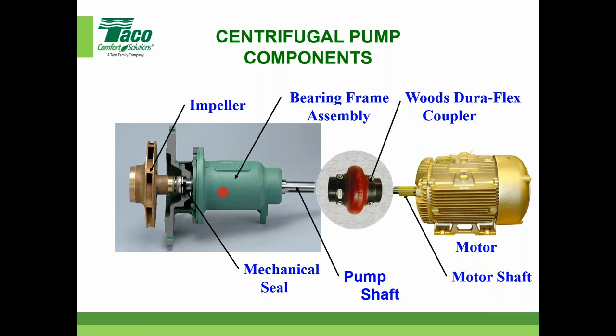So bearing frames, we have 4, 5, 6 different models. Our current FI model, the ones we make day in and day out in Cranston, Rhode Island, have sealed for life bearings in there, so they do not require any lubrication. There are bearings in there that help the shafts to stay in alignment, but those bearings are sealed for life. They do not require any lubrication, and they should last 15, 20, 25 years. I mean, they're very, very sturdy. So the L10 life is really exceptional, as long as everything's in proper alignment, right? So those shafts have to be in proper alignment.